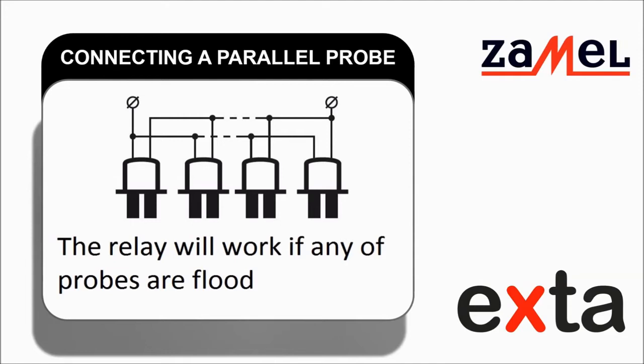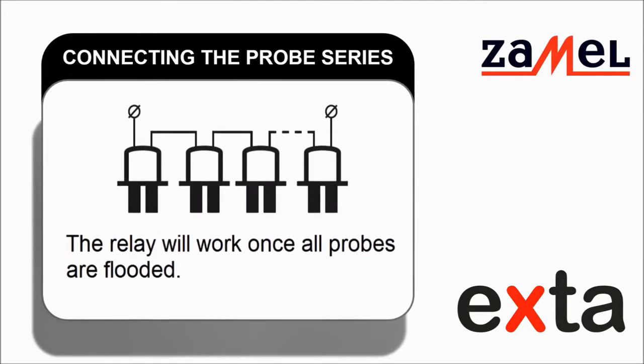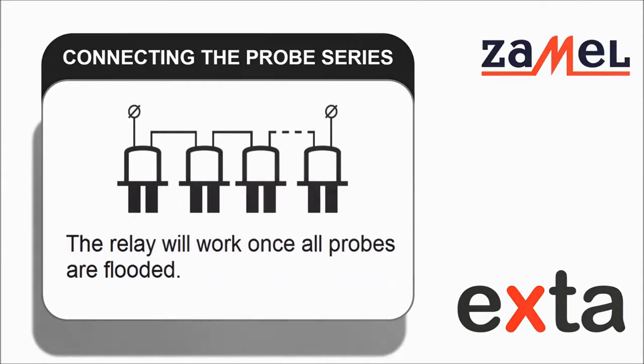The connection of parallel probes forces the relay to operate in the event of flooding of any of the probes. The connection of the serial probes forces the relay to operate in the event of simultaneous flooding of all probes.